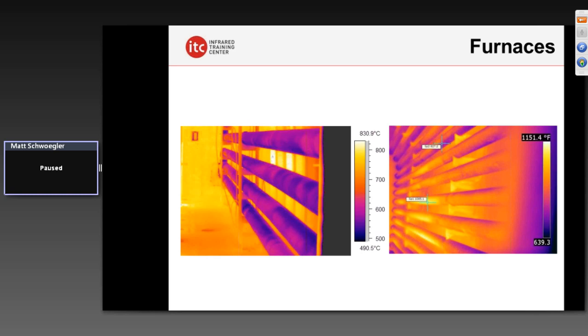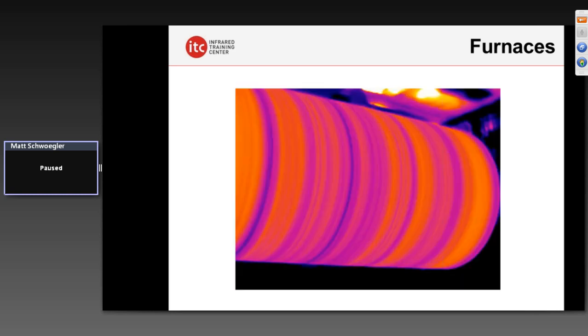Your typical long-wave camera would not be able to do this because the flame is in the way. But in the mid-wavelengths with the right type of filter, we can actually see through the flame — it effectively removes the fire from the frame — and we can clearly evaluate the surface temperatures and patterns on these tubes inside the furnace, including the efficiency of the burners.